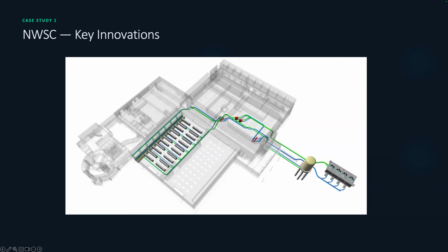Did you ever actually do testing scenarios where you did these power failures or cooling failures, or is it all just simulated? So we actually experienced, when I was there, 2 cooling failures, and one of them we rode through with flying colors, and the second one we did not get as much time as we'd anticipated. In both cases, we didn't cause any real damage, but the first failure scenario was actually a control sequence where the valving failed. And so we shut a portion of the valving off, which caused the head pressure to go out of design conditions, and so the pump shut off.